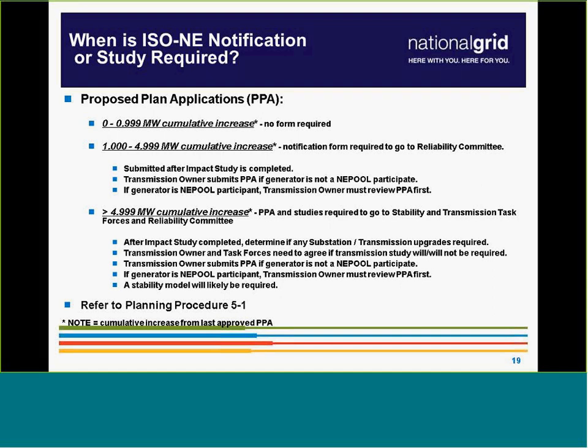We do our analysis on the impact at that minimum load, maximum generation scenario. From our local distribution network, the 13,000 volt system, once you get enough of that, it starts to affect the 150,000 volt transmission system, which is happening. Through the substation in West Warren, going to West Road South, we're looking at potentially having to replace a 40 megawatt transformer just because of the amount of solar that wants to connect to that substation.